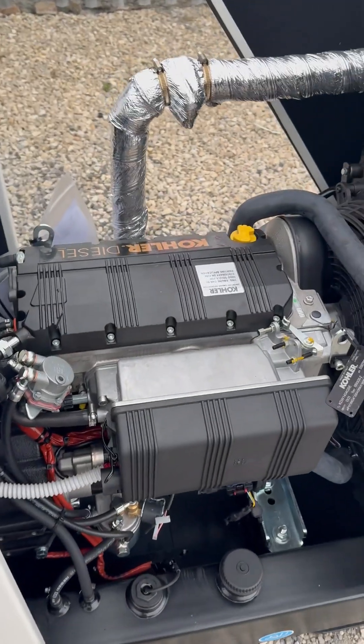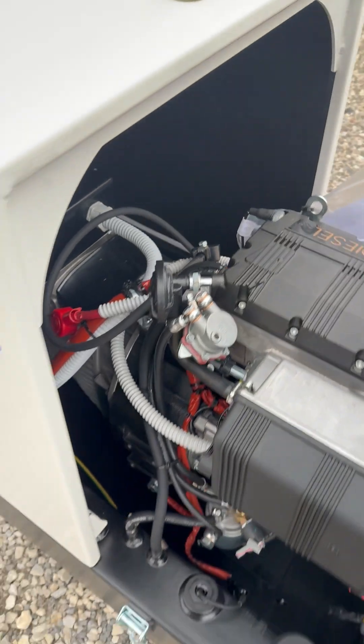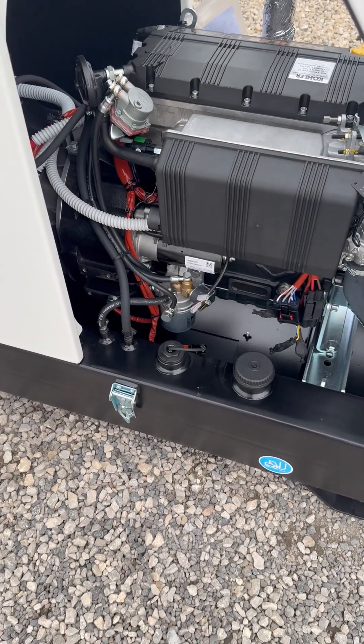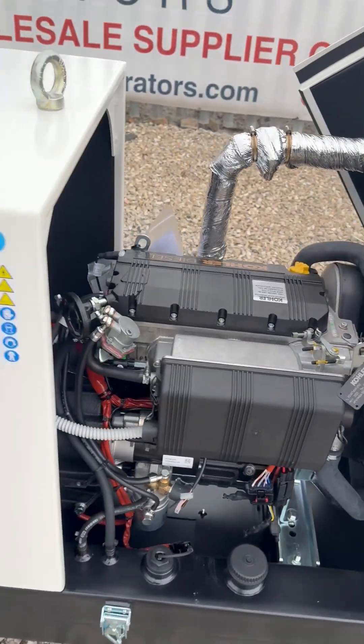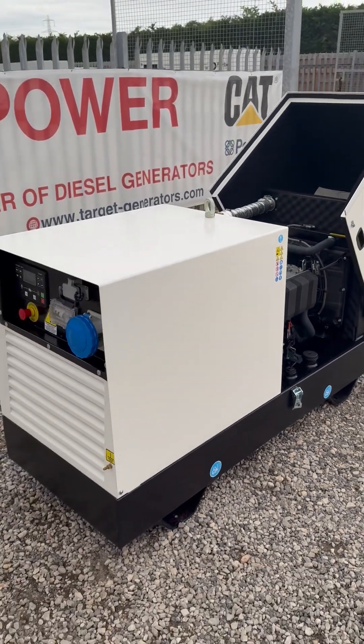It comes with a Kohler engine manufactured in Italy, running at 3000 RPM, coupled to a Linz alternator which has an AVR on there. Internal filling — so you fill directly into the base. You should get 24 hours running at 75% load. It's designed for emergency applications or off-grid applications.